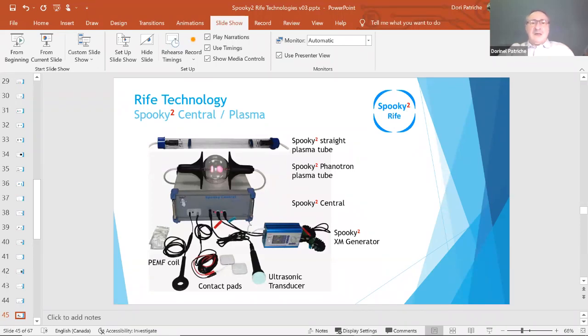The other accessories are the PMF coil, which you can see at the lower left corner, the contact pads, and the ultrasonic transducer. These accessories can be used independently, but it is recommended to use them with the plasma tube. When used with plasma, the PMF coil will create electroporation, which means it will temporarily open the membrane of the pathogen cells, facilitating the penetration of plasma. Without plasma, PMF can be used to effectively control all types of pain, particularly in bones and joints. PMF has a fixed frequency and doesn't require a frequency input from a generator if you use it independently. Because of the magnetic component of the signal, it is not safe to use with pacemakers and other electronic implants.